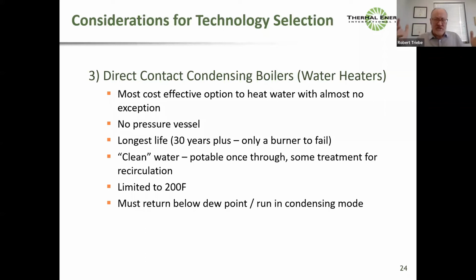And now, we just extend it really, because now we just put a burner in them. So now with a direct contact condensing boiler, so now this is the shower over the burner, it is absolutely without doubt the most cost-effective option to heat water without exception, honestly. If you've just got a water stream that you've got to heat to 80 degrees Celsius and you're going to use a fossil fuel, natural gas, this is absolutely the most cost-effective way to do it. There's no pressure vessel involved. That's why, because it's a shower and a flame. So you've got a burner, as does a boiler, but you've got no pressure vessel. And so it becomes a very cost-effective and simple installation.